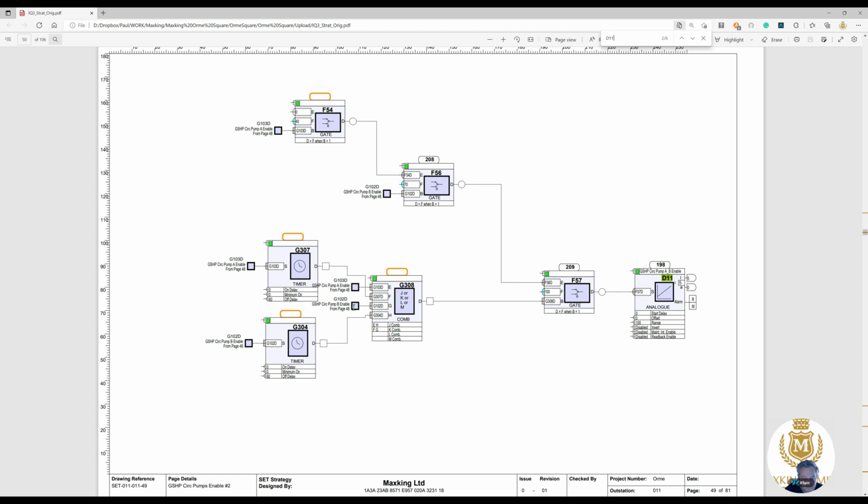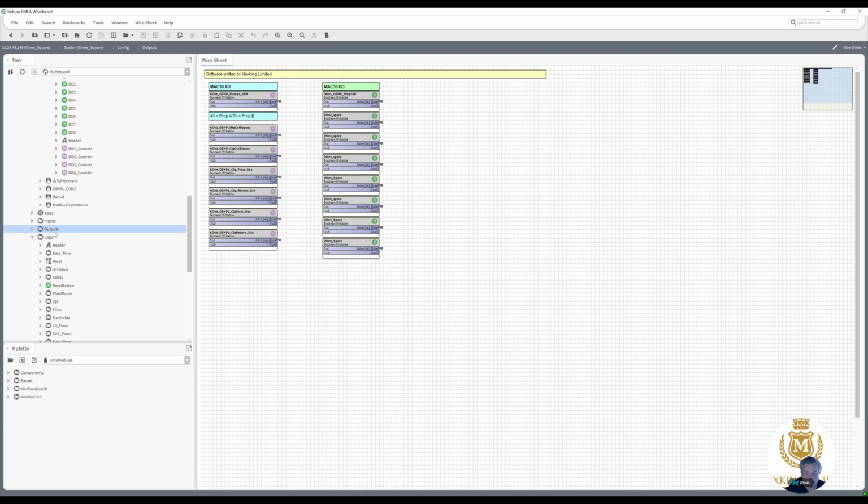The timers have an off delay of 60 seconds in this one, and an off delay of 60 seconds in this one, and this has got a standard Trend combi block giving the output into B. So when you don't have an input there, B doesn't equal 1, so D, the output there, is going to be 100, and 100 is basically stop, like a 0 is stop on these 2RM units. So that's the outputs done.